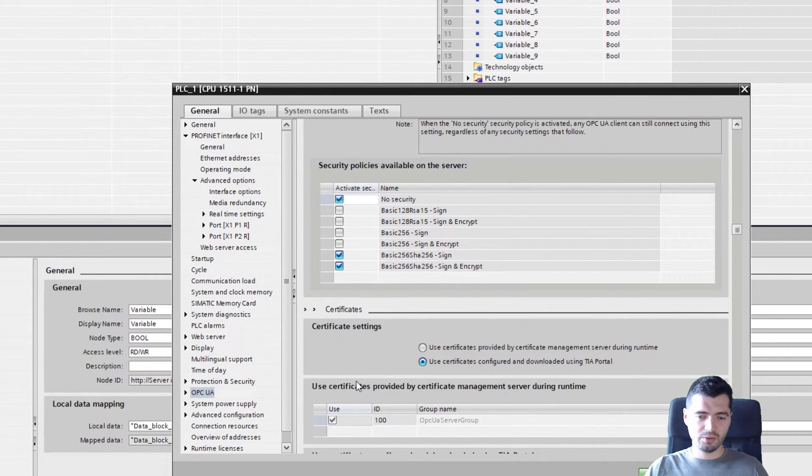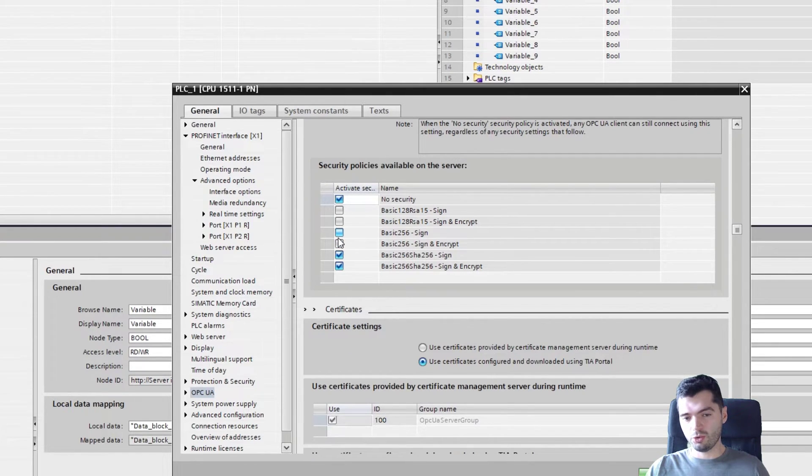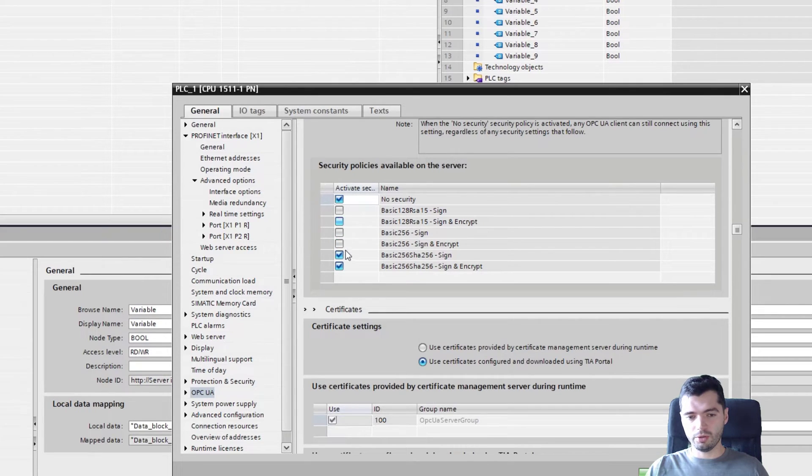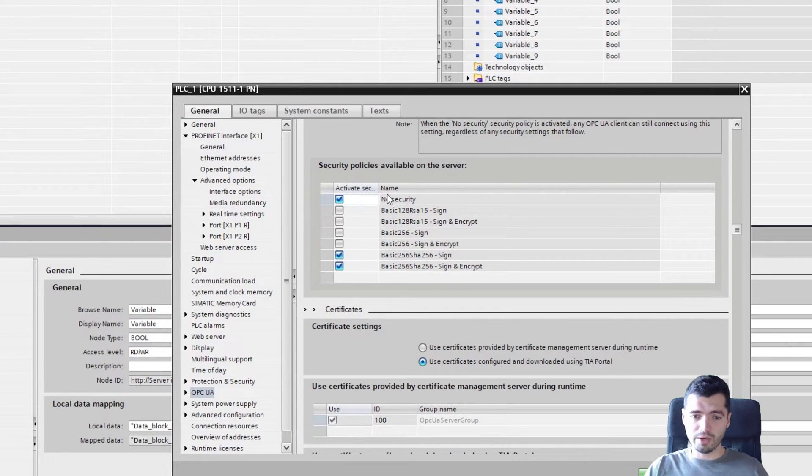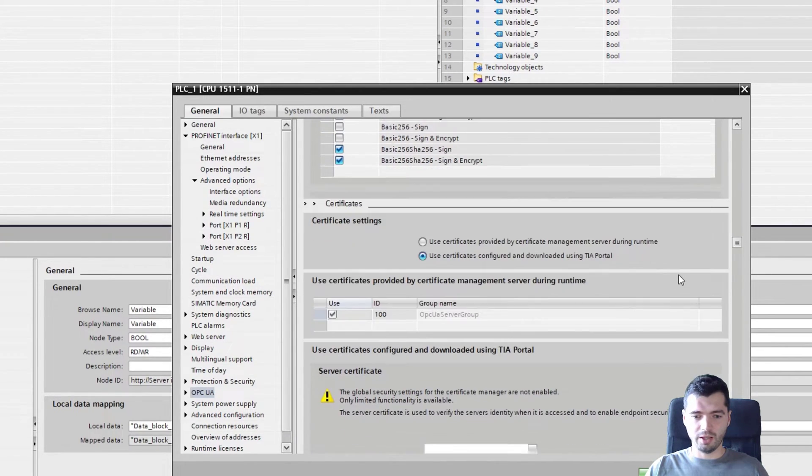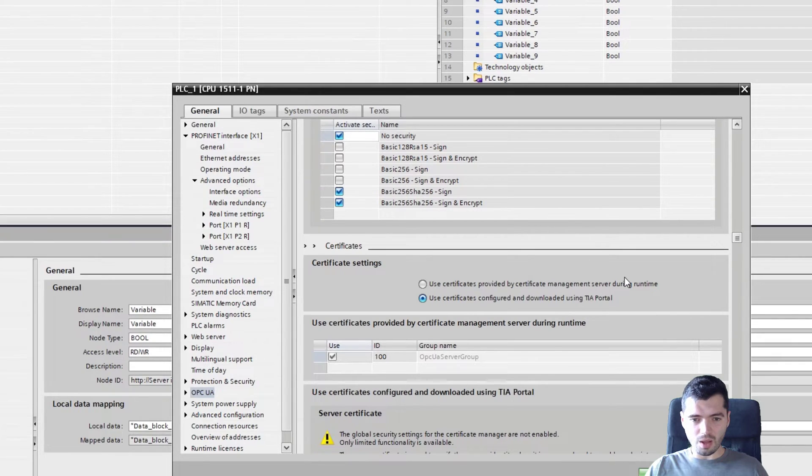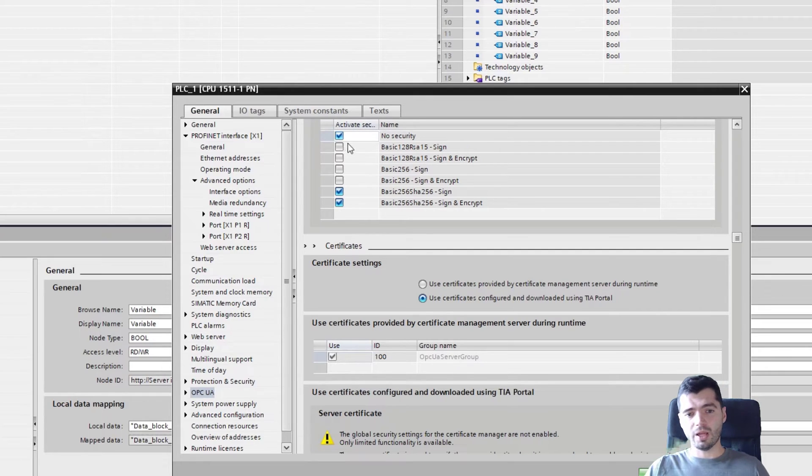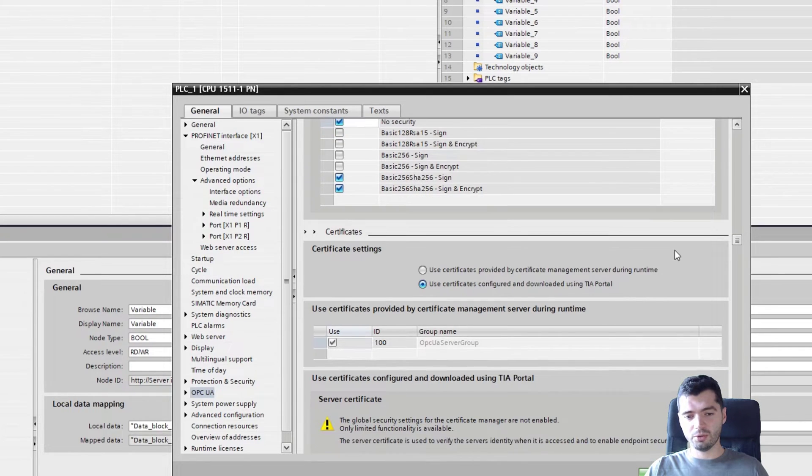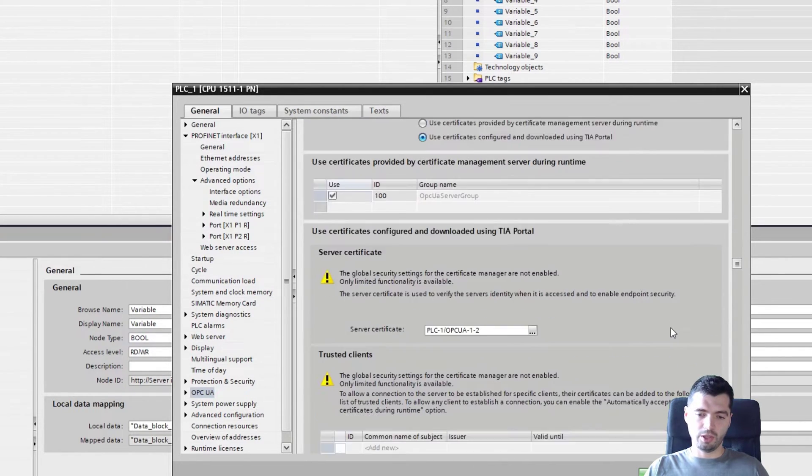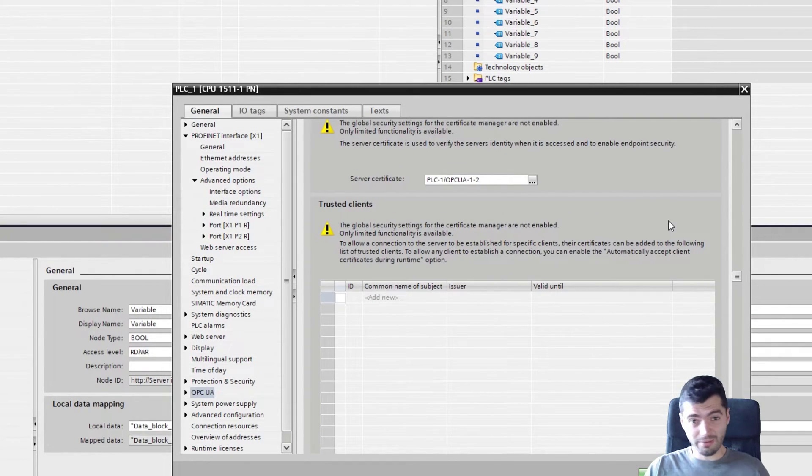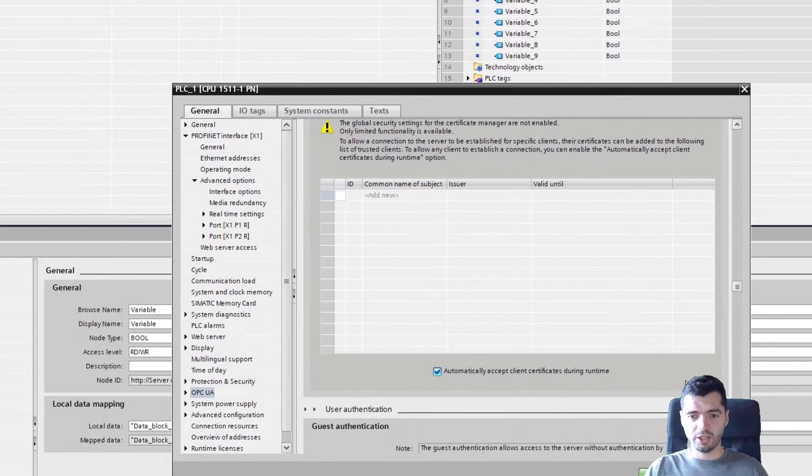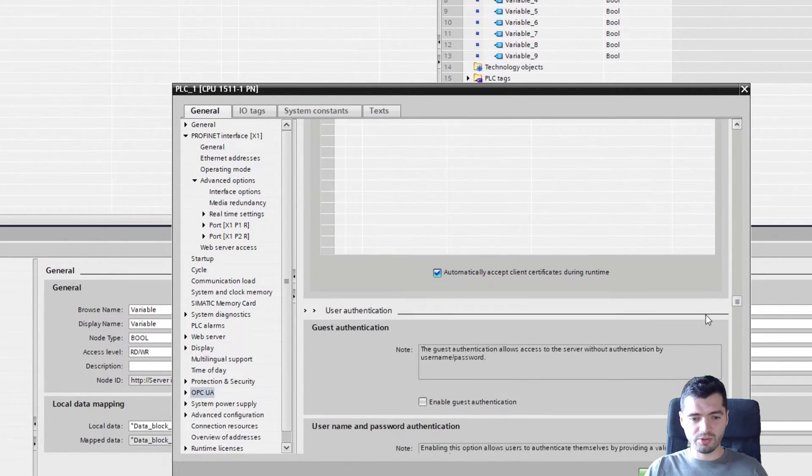Then we have security policies. If we are using certificates, then you need to make sure that whatever security policy you are using is activated here. If you are using no security, then this means that you will be able to connect to the server without any certificates. If you want to prevent this because you are cybersecurity aware, then you would deactivate the security policy none and load the necessary certificates. And if this is of interest, I guess we could make another video specifically on the certificates around OPC UA.